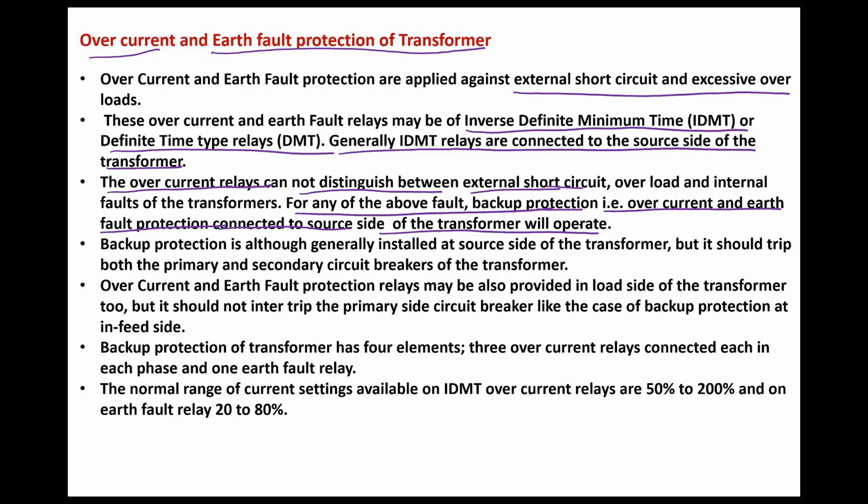One more important point is that this overcurrent and earth fault protection in a transformer is called backup protection. Why is it called backup protection? To take care of faults inside the transformer, we already have three special relays: overflux relay, Buchholz relay, and differential relay.